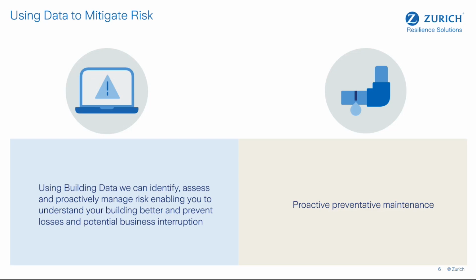That was spotted because of the building data, and we were able to mitigate that risk by reducing the temperature of the storage water. Another thing I'm going to talk about is air quality. Following on from the pandemic, it's imperative that in the working environment we have fresh air flowing in, and there are various bits of data that could be pulled from the building, allowing us to make a judgment as to the level of air quality.